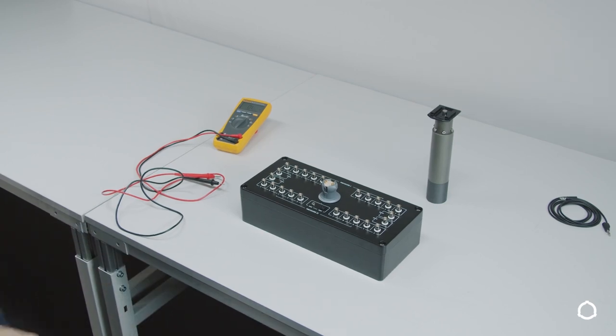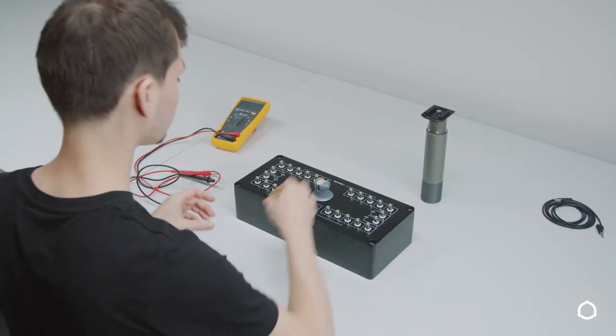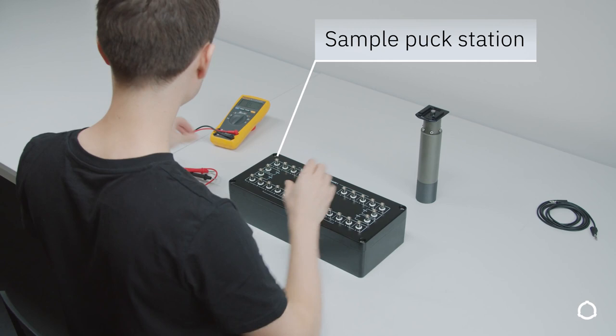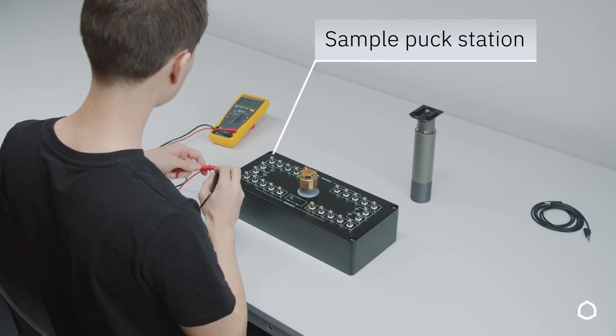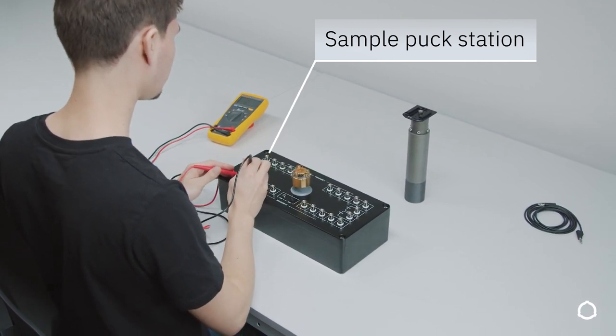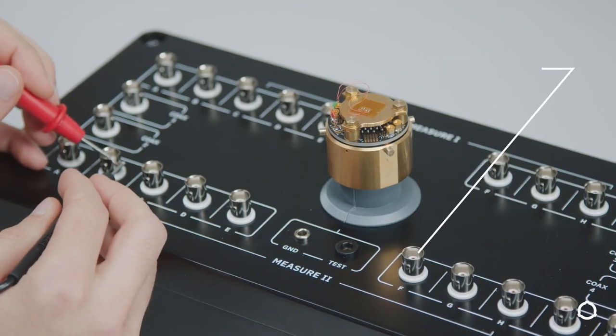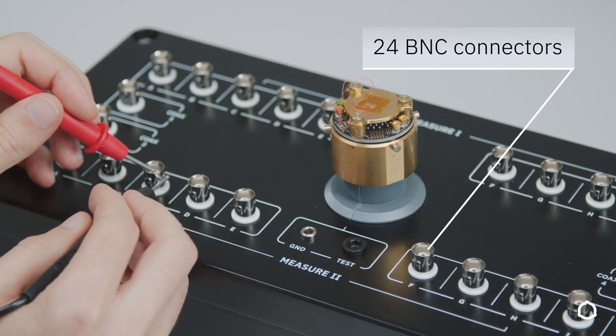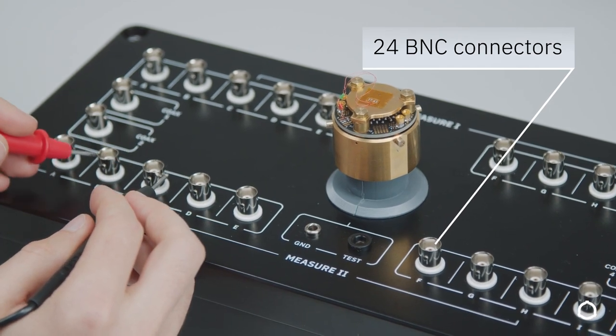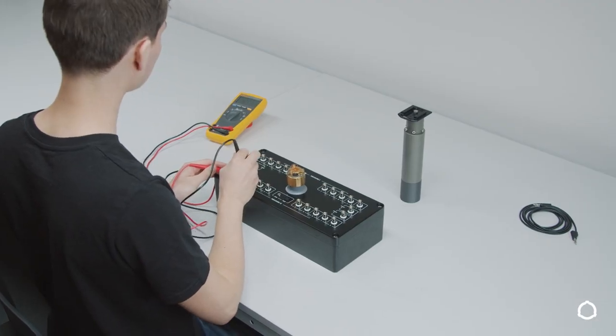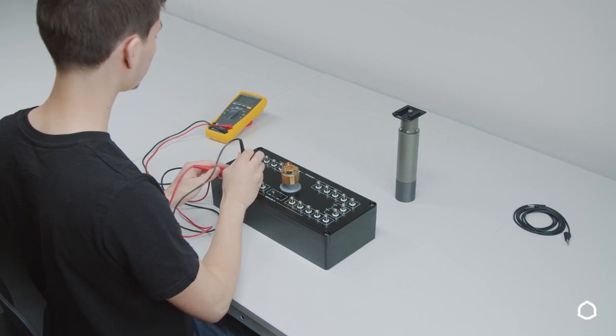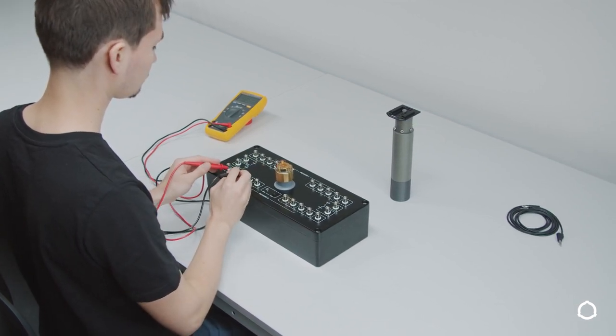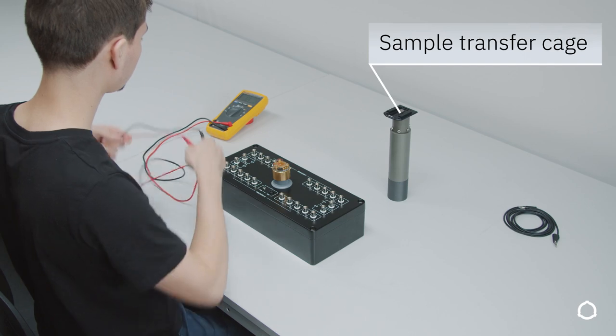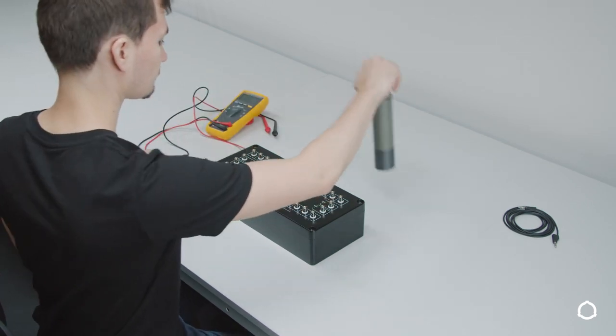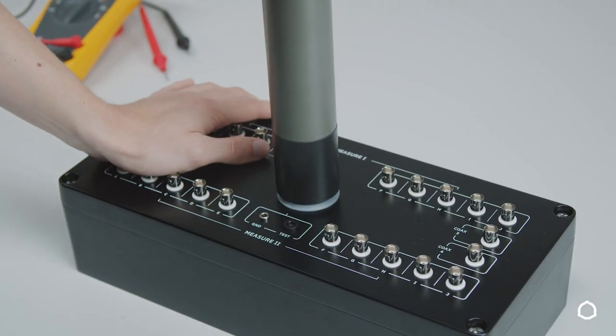After preparing the sample on the puck, a final test can be carried out on our sample puck station. In this example, we just checked that all solder connections are good using a standard voltmeter. However, the sample puck station features BNC connectors for all puck lines, allowing for complex room temperature tests involving more sophisticated measurement electronics. Once we are sure that our sample is prepared properly, the sample puck is picked up using the sample transfer cage. A special mechanism locks the sample puck in the transfer cage and the puck can be safely transported to the cryostat.